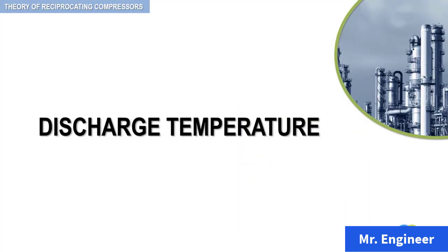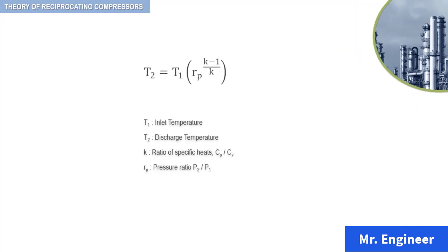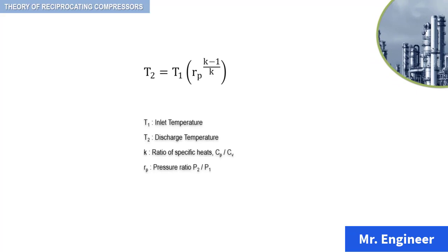The discharge temperature of a reciprocating compressor stage can be calculated using the following formula. Here, T1 is the absolute inlet temperature, T2 is the absolute discharge temperature, K is the ratio of specific heats, and RP is the pressure ratio.